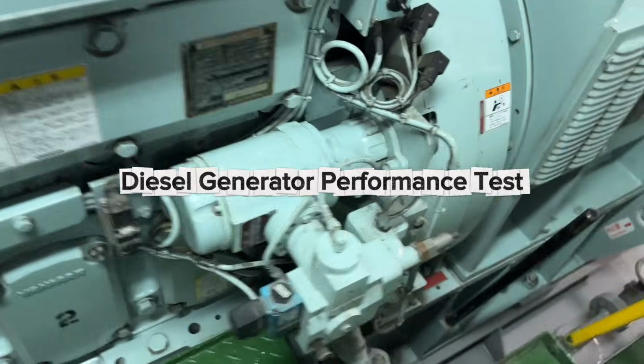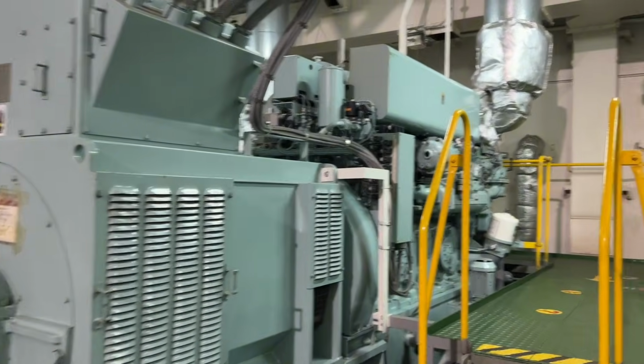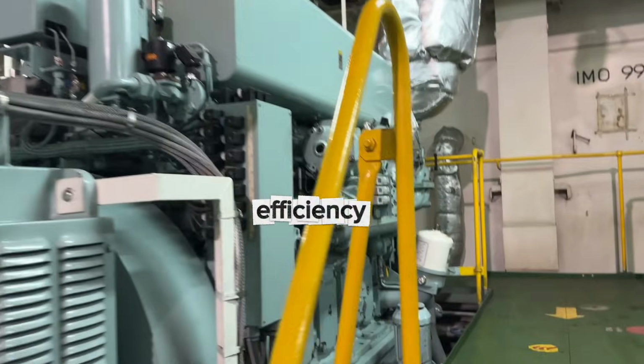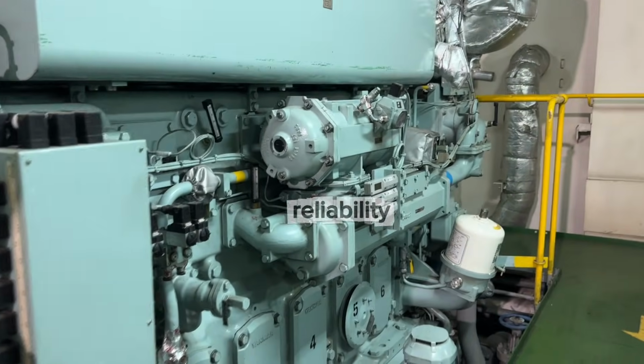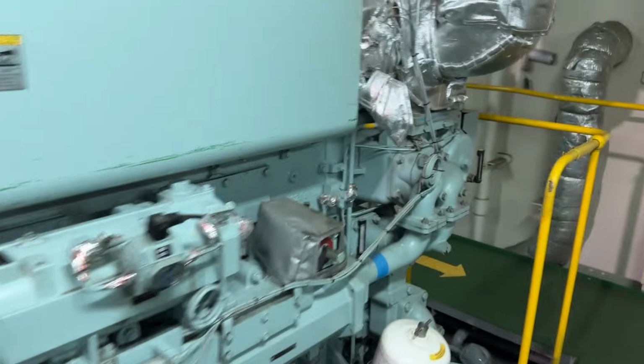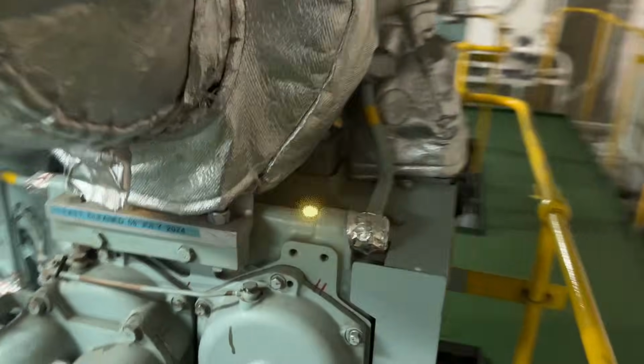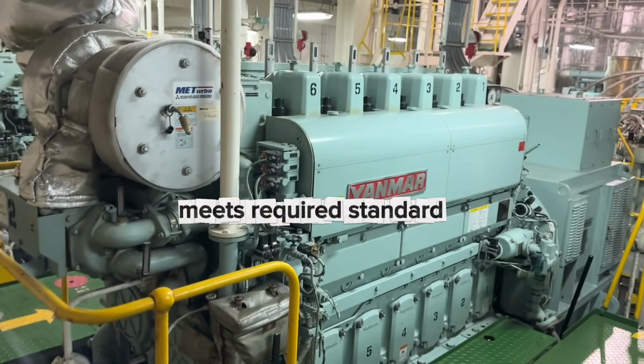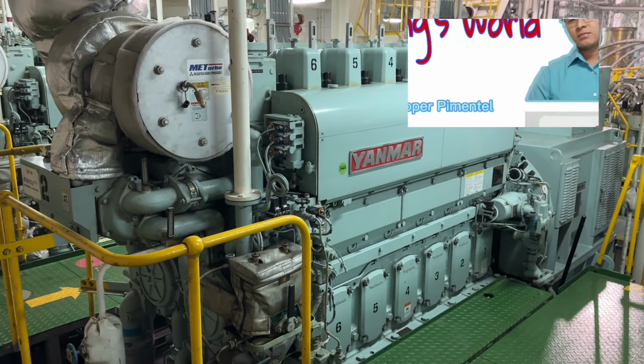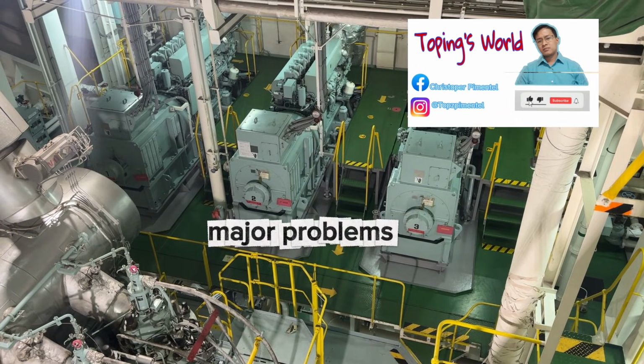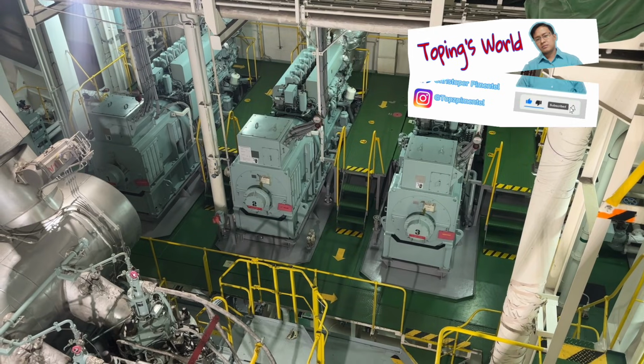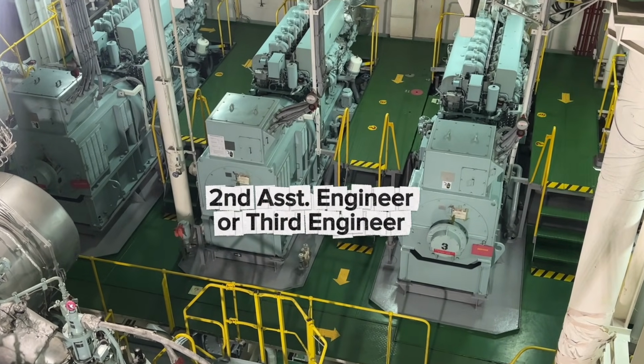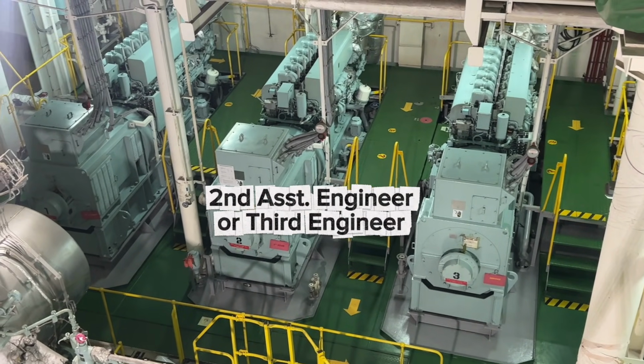A diesel generator performance test is a procedure to evaluate a diesel generator's efficiency, capacity, and reliability. It checks if the diesel generator is functioning as expected, meets required standards, and identifies potential issues before they become major problems. It's usually done once a month by a second assistant engineer or third engineer.